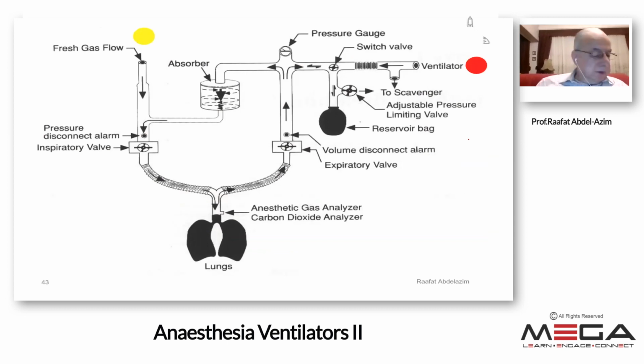This is a very important point. The ventilator pushes its content, this is the tidal volume, into the breathing circuit. So there is a connection into the breathing circuit. The breathing circuit consists of inspiratory limb and expiratory limb, starting with inspiratory valve, and this is the expiratory valve. Each valve allows passage of gases in one direction only. So the inspiratory one into the patient's lung and the expiratory valve out of the patient's lung.